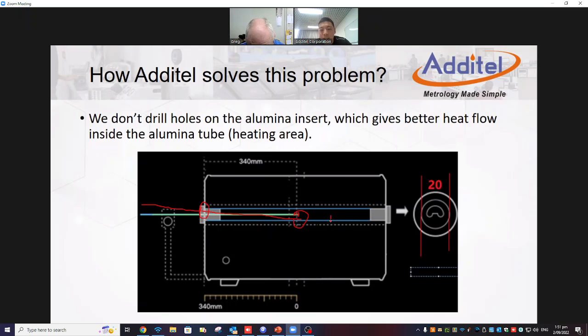We may have a temperature difference from center to the bottom, maybe 0.3 degrees Celsius. This is okay for industrial customers, but for lab users that's a pretty huge temperature difference. We may have a significant difference between two probes because they're not touching each other, so there's no high temperature transferring efficiency between them. They may have a temperature difference of just 0.1 degrees Celsius, but this is not acceptable for lab user customers.